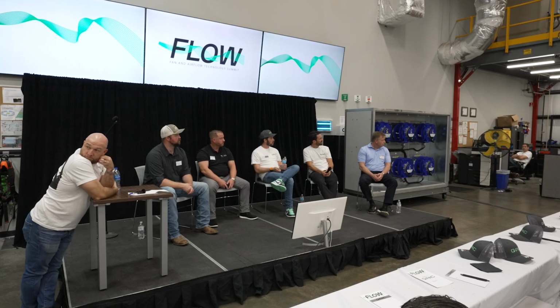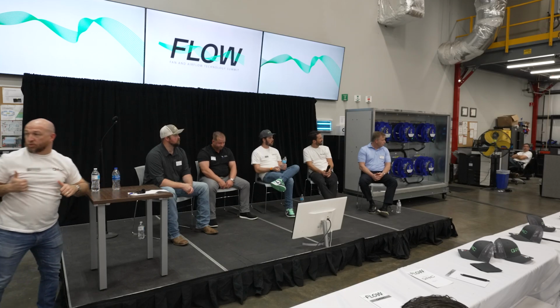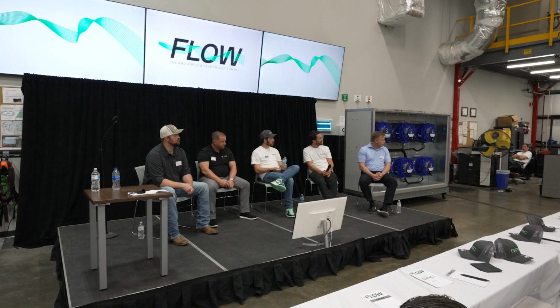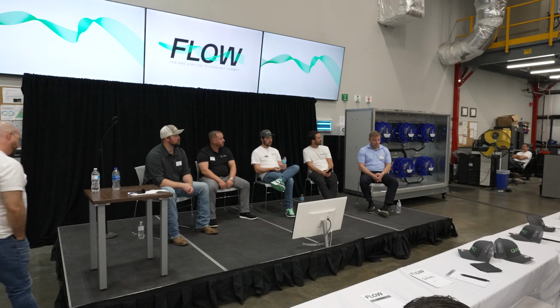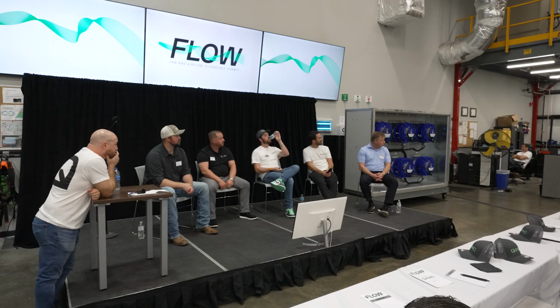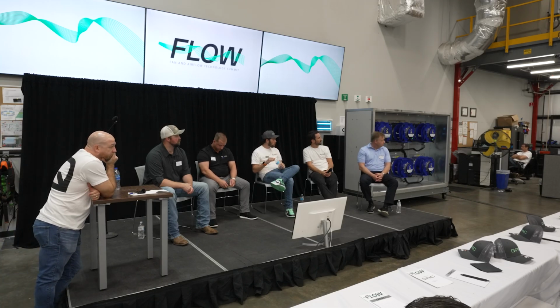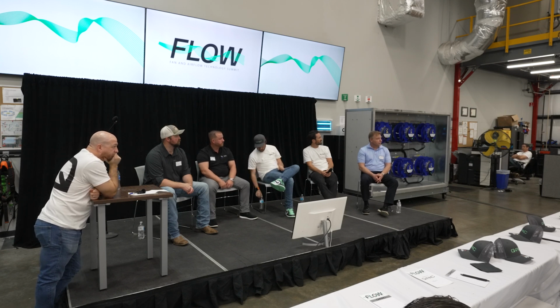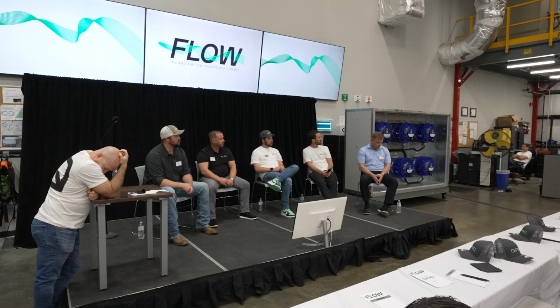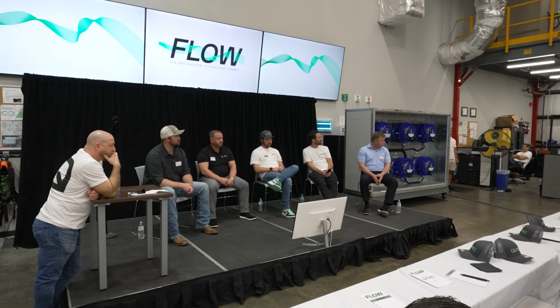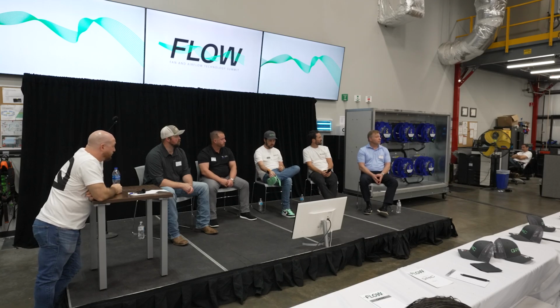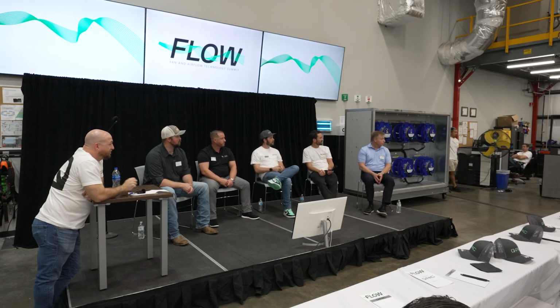The motor isn't tensioned properly, hasn't been greased or serviced in a long time. There are so many variables with the VFD motor system that cause these things to underperform over time. I know there's debate about the ECM motor versus the traditional drive motor and the energy efficiency there, but practically, looking at that many building samples and that many VFDs and traditional motors with that much inefficiency over time, I feel like that's a selling point we could be discussing in the market. Just a real world thought from me.